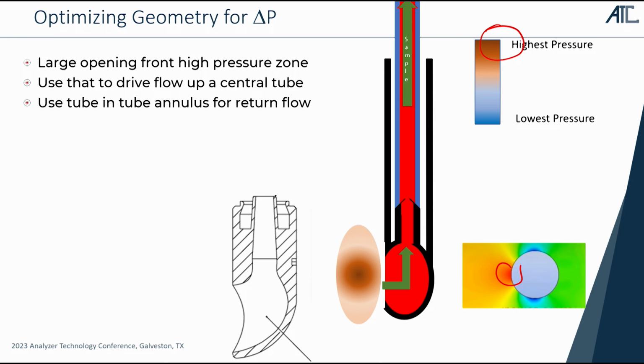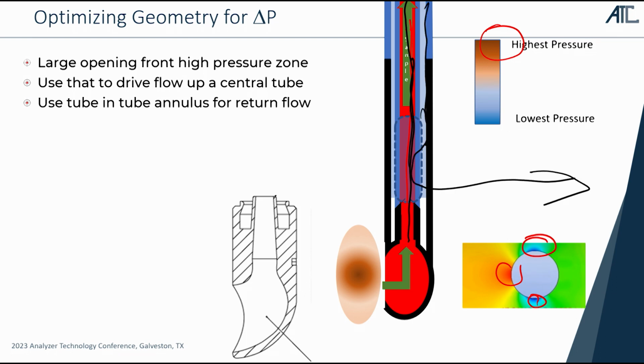At the same time as fluid is flowing and impacting on this probe, there's low pressure regions on the side. So we said over here on the sides of the tube, there's going to be a low pressure region. So we make a big set of ports on either side of the probe body, and those become our return points. Fluid that's gone up through the center region returns back through this annular region and goes out those ports and returns back into the process lines. So we put large ports on the sides, lots of surface area, and there's a place for the fluid to escape back into the process.